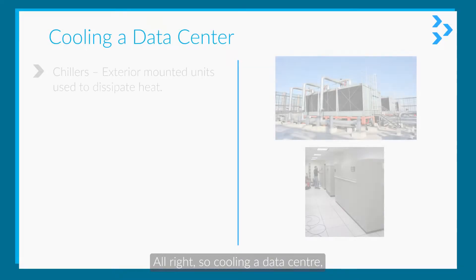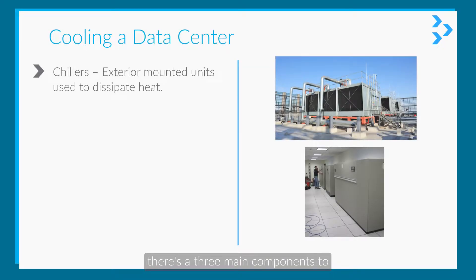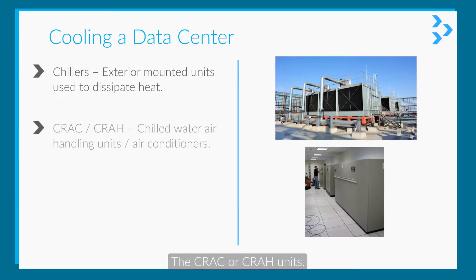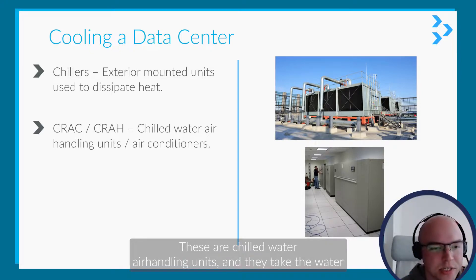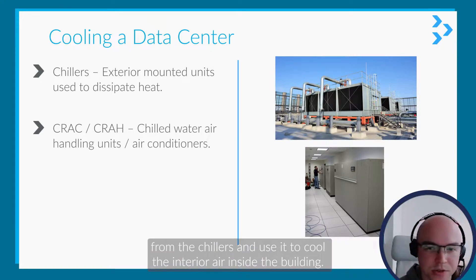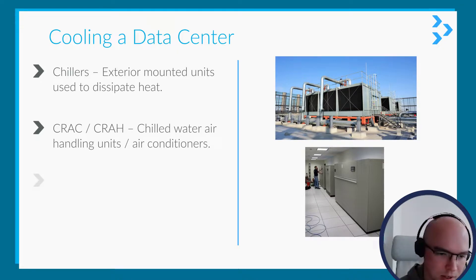So, cooling a data center. There are three main components to this. There are the chillers, which are exterior-mounted units used to dissipate the heat. The CRAC or CRAH units — these are chilled water air handling units — and they take the water from the chillers and use it to cool the interior air inside the building.